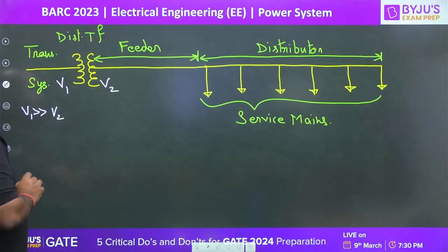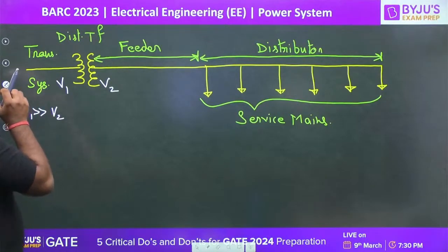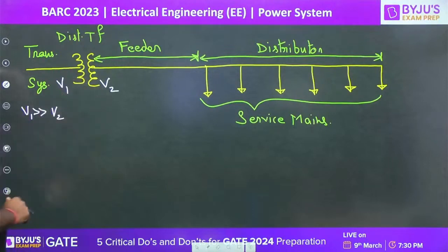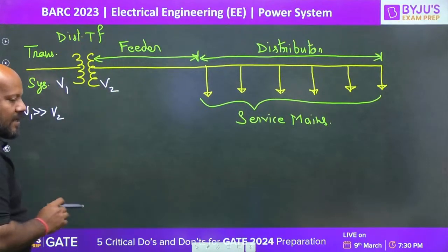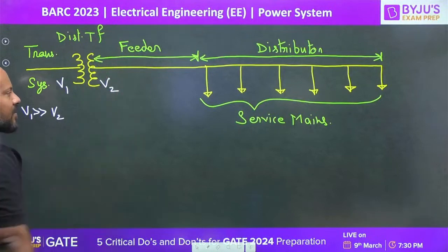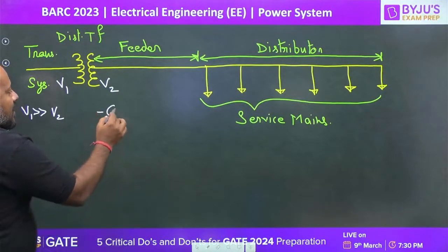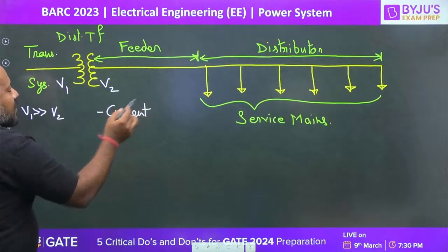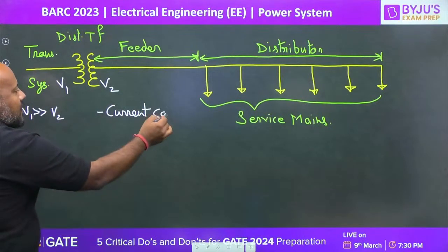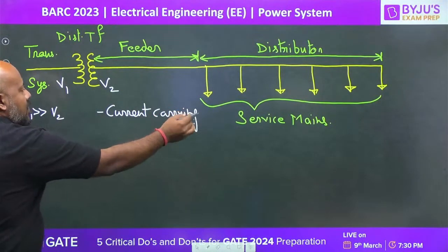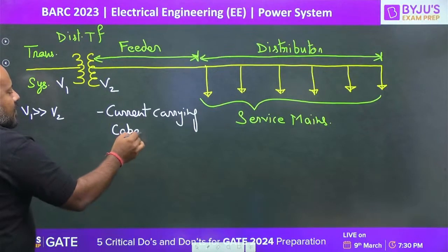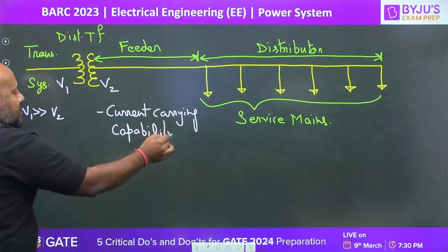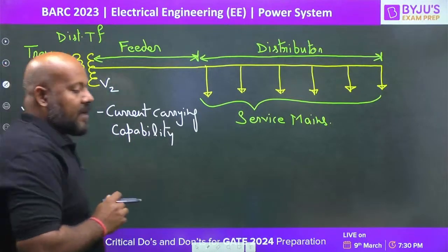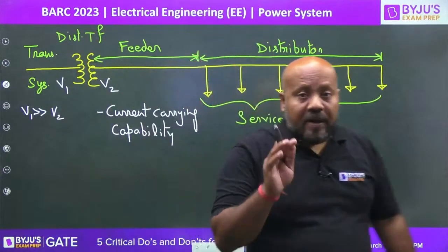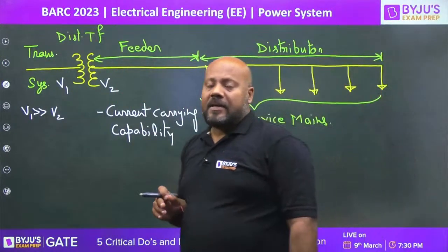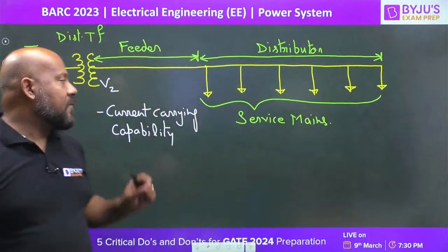For a given power value, if voltage is severely reduced, the current is going to be severely increased. It means there is going to be bulk amount of current. So the current carrying capability is one important criteria. And because bulk amount of current is going to be carried by the feeder, temperature stability and temperature rise is going to be one important criteria for designing the feeder.